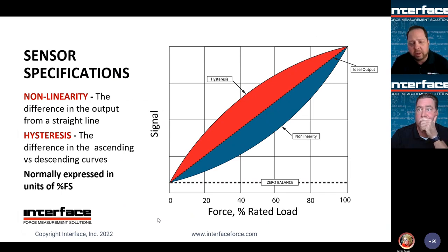So digging into some of the specifications you saw earlier for the load cell, this is a bit of an exaggerated plot to help define them. There are two primary factors that result from a calibration with regards to load cell performance, and that's nonlinearity and hysteresis. These are the more common aspects of a cal. In this diagram we talk about an ideal, perfectly linear output. Typically, though, when you calibrate a sensor, as we saw, there'll be a slight curve in that output as you ascend to the rated full-scale range. In this case, the blue portion is the slightly nonlinear ascending load points. And then the exaggerated hysteresis on the top side is when you take the descending points to capture the hysteresis value. You end up with a percent deviation off an ideal straight line. Those percent deviations define the nonlinearity for the ascending side, and then the descending side hysteresis, also a percent deviation from linear output.